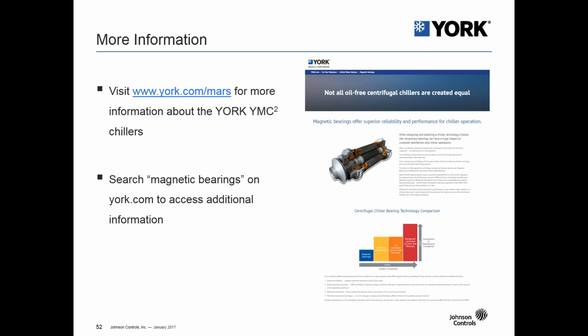Thank you, Craig. A few more questions are coming in. One is asking, how much time is actually available with operation below 55 degrees? So that's going to vary widely based upon any specific location or chiller installation. However, there are significant amount of hours available well below 65 and 55. We would recommend that for every chiller installation or application a full weather analysis be reviewed to see how many hours are available at any of the temperatures.